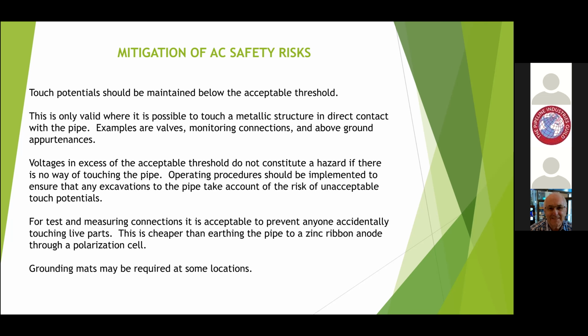Voltage gradients are easy to picture if you imagine they're exactly the same as a gradient in the soil. If you have a very steep hill, the difference between one leg and the other is quite steep, and therefore it's more difficult to walk because of that difference. It's the same with voltage gradients in the soil: if you've got a big gradient, with one leg at one potential and another leg at another potential, the difference can be enough for current to flow through your body.